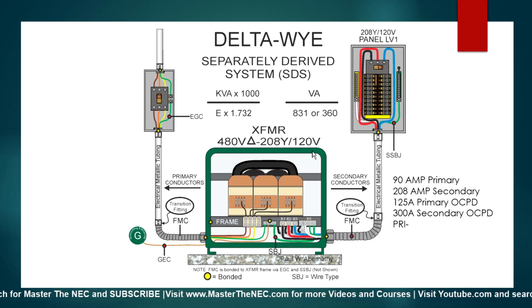So even if this is 208, I have to know my calculated load. Even though this might be a 300 amp device and these conductors are rated for 300 amperes, my load itself cannot exceed the maximum output of this transformer. Otherwise, I'm going to cause problems with this transformer. So I might have only 190 amps of load on a 300 amp breaker.